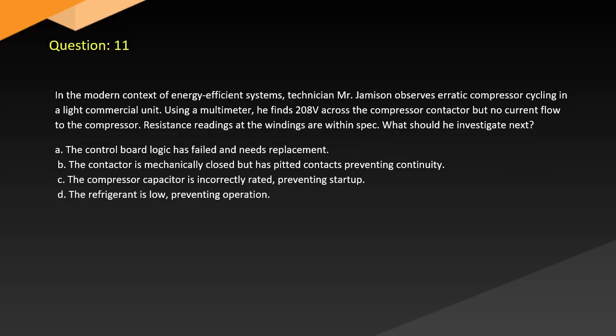Question 11. In a modern context of energy-efficient systems, technician Mr. Jameson observes erratic compressor cycling in a light commercial unit. Using a multimeter, he finds 208 V across the compressor contactor but no current flow to the compressor. Resistance readings at the windings are within spec. What should he investigate next?